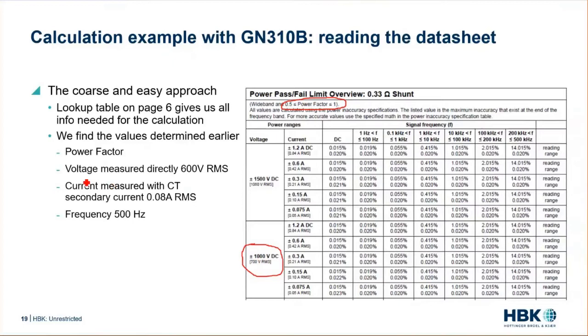The current measured with the CT results in a secondary current of 0.08 amps RMS, so we are in that current input range. The frequency is 500 hertz, so we go into the corresponding column. Combining that column with the relevant row tells us we will have a 0.055 percent of reading error and a 0.02 percent of range error.